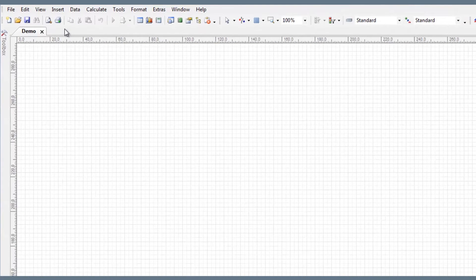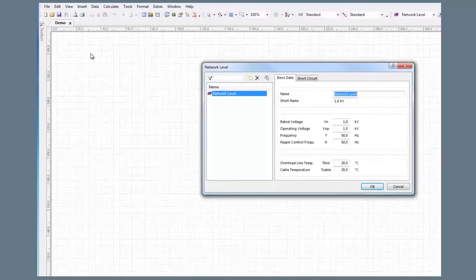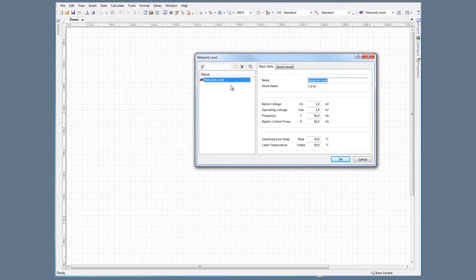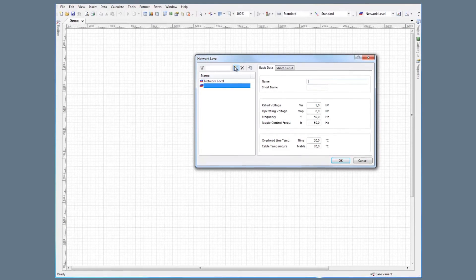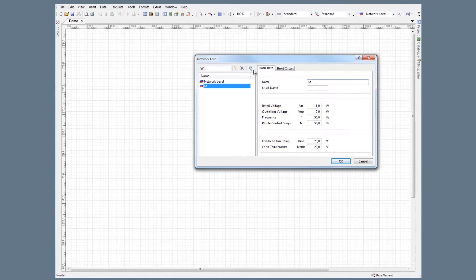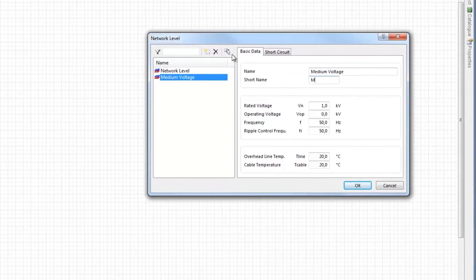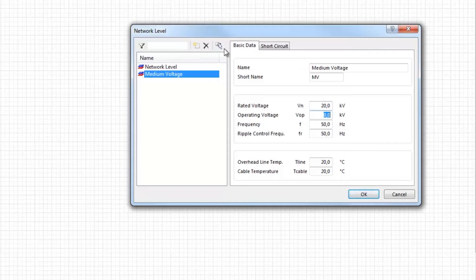Now that we've created a file, it's time to create our network. In PSS SINCAL, all network elements must be assigned to an electrical subnetwork. PSS SINCAL creates the subnetwork with the network level. To create the network level, click Insert, Network Level. Then click New to create a new network level and edit this new entry on the right-hand side of the dialog box. A new network level, medium voltage, with 20kV rated voltage and operating voltage is now added.